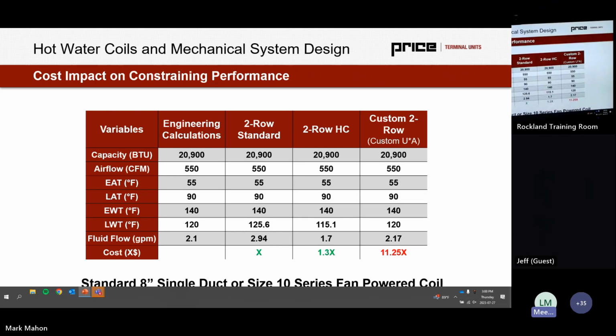But when we look at custom coils, we're looking at swapping over from a full commodity style manufacturing facility to a job shop, and that is expensive. So that's why we see a trade-off where we're going to have higher GPMs and lower delta Ts, or lower GPMs and higher delta Ts. We're going to get close, but it's because we don't have full control over the way we make the coil.